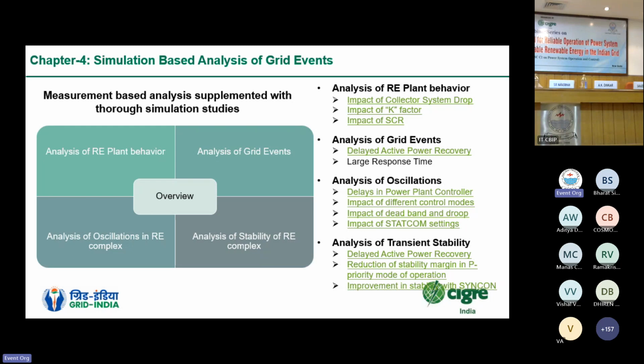Then in the analysis of oscillations, it was identified that there were certain delays in the power plant controllers. Power plant controllers were not fast enough to exactly follow the voltages. It was also identified that different control modes available in the plants have different impacts, and tweaking of the control modes can help to achieve stability. Deadband and droop were also identified as parameters which can be tweaked to do some tuning of the plant response.